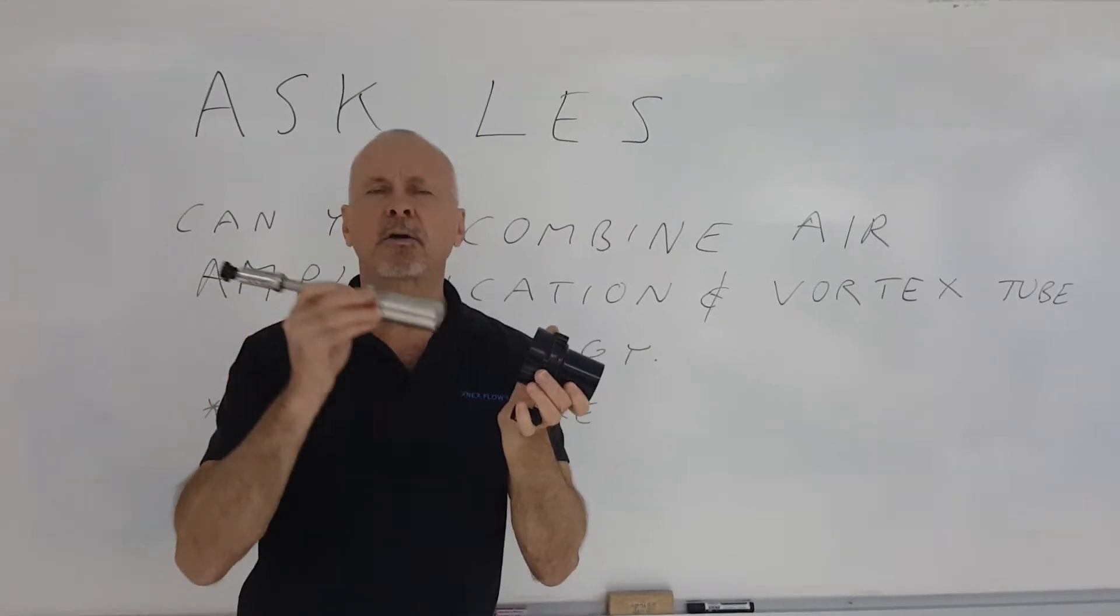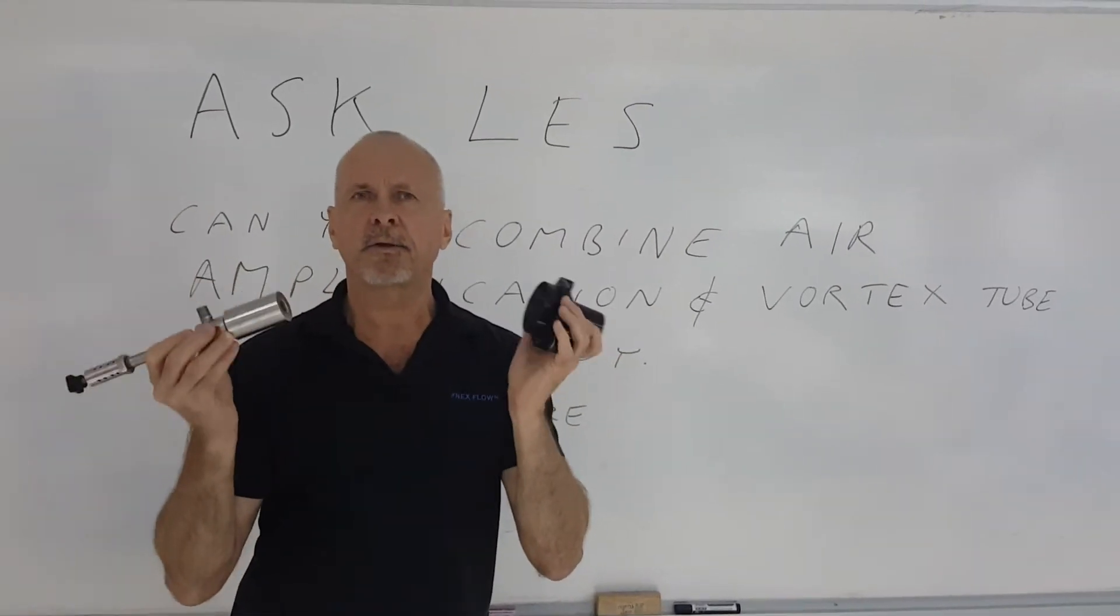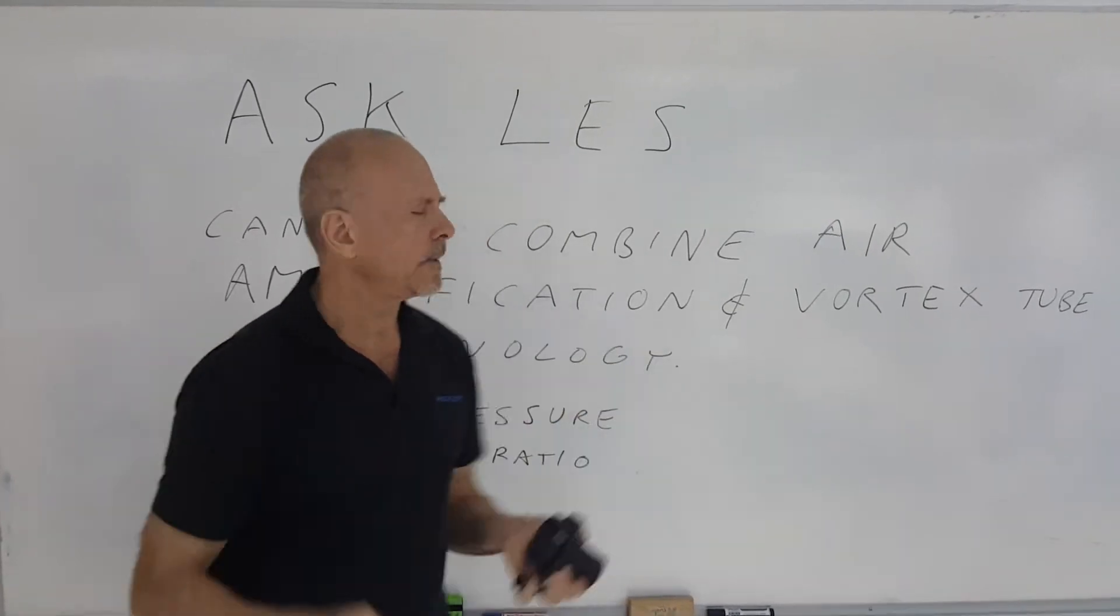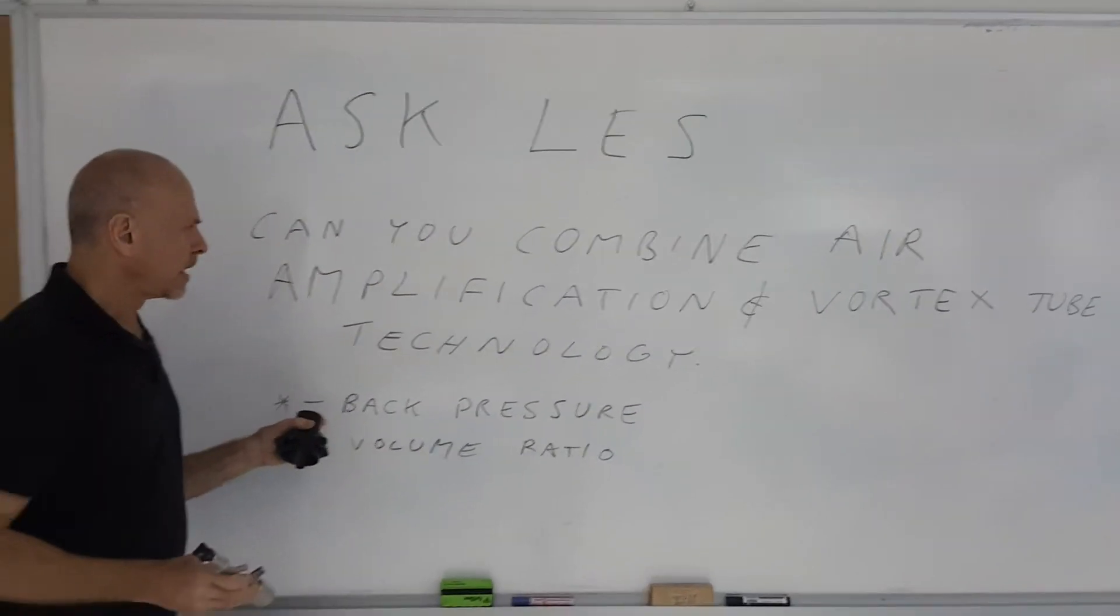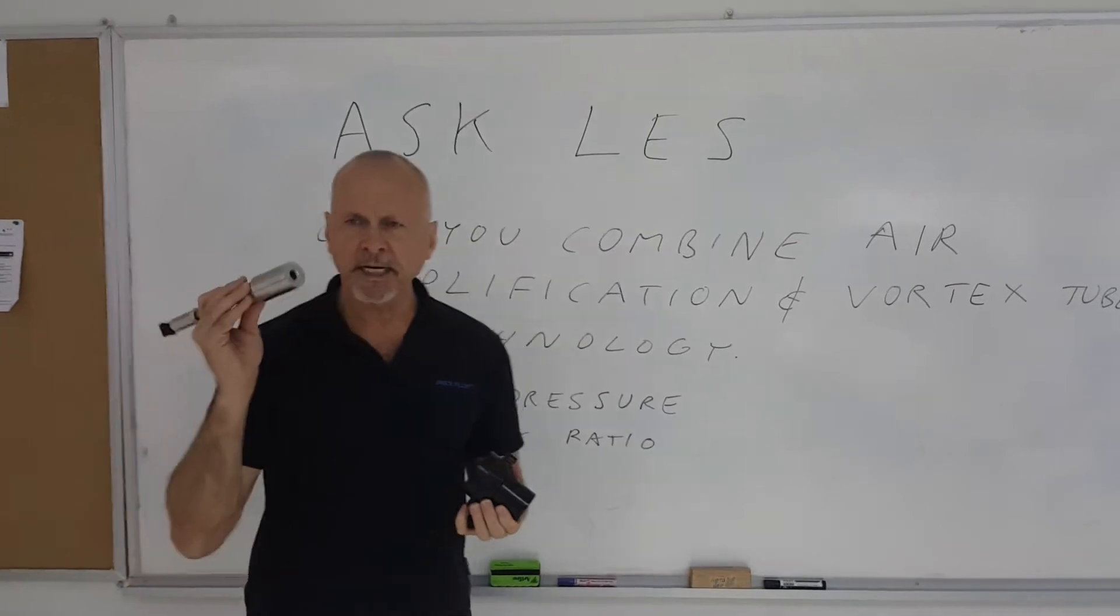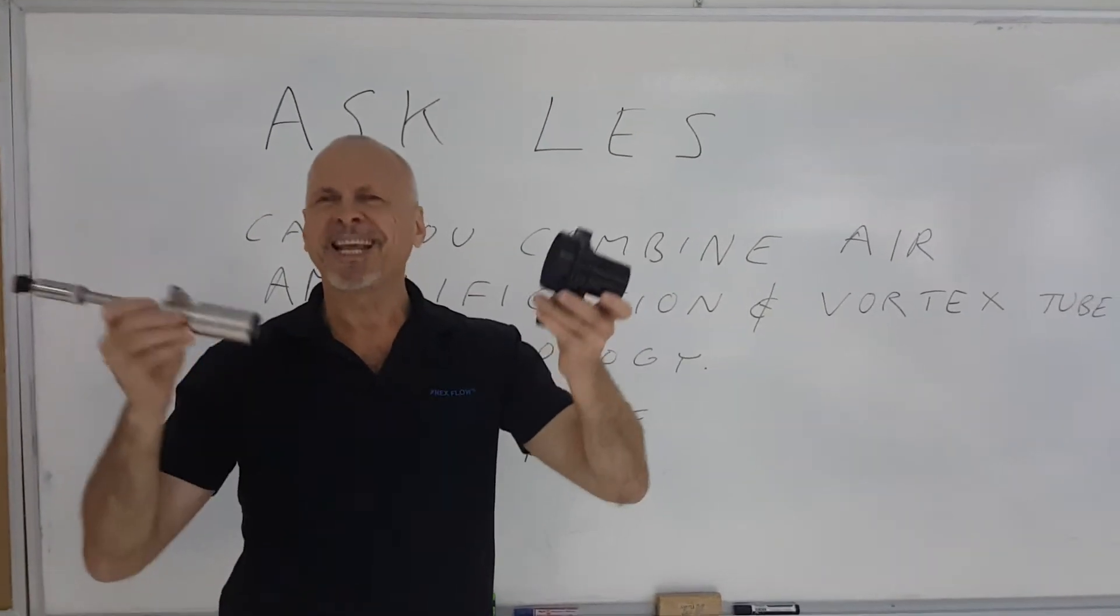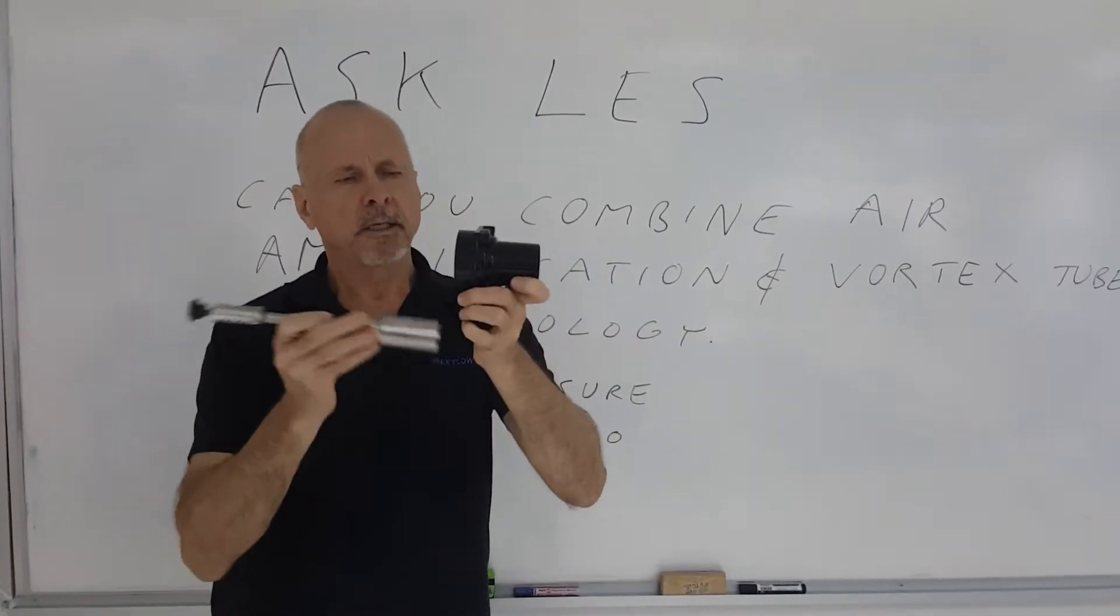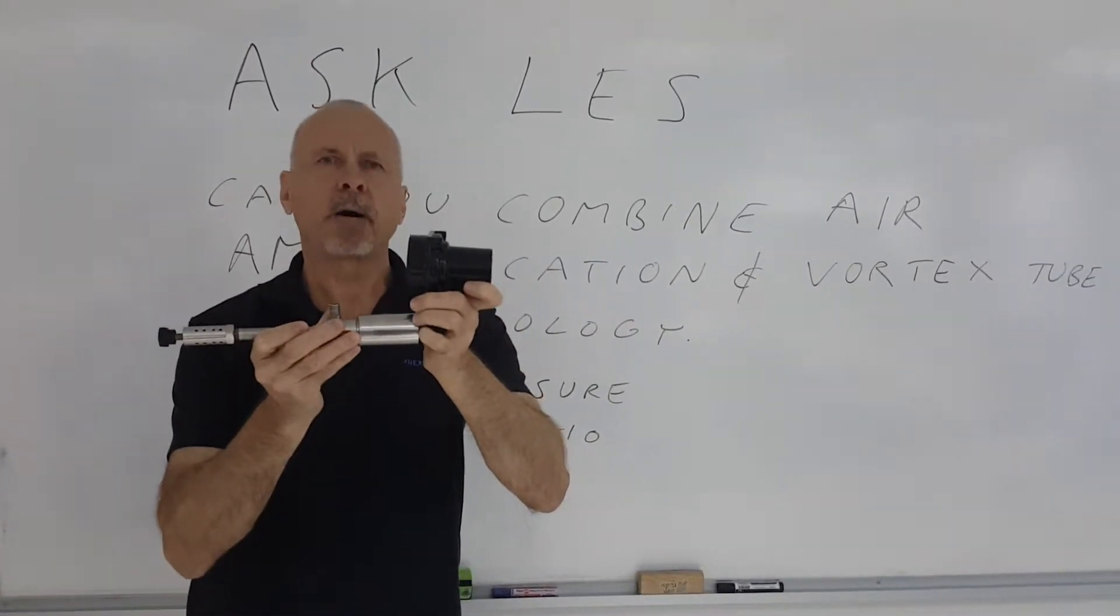Can I combine it with a vortex tube? Generally, you cannot. Here's why: first of all, back pressure. If I take the vortex tube and put it in line—say the compressed air supply goes into the vortex tube and then the cold air is piped directly to power the air amplifier—it just will not work.